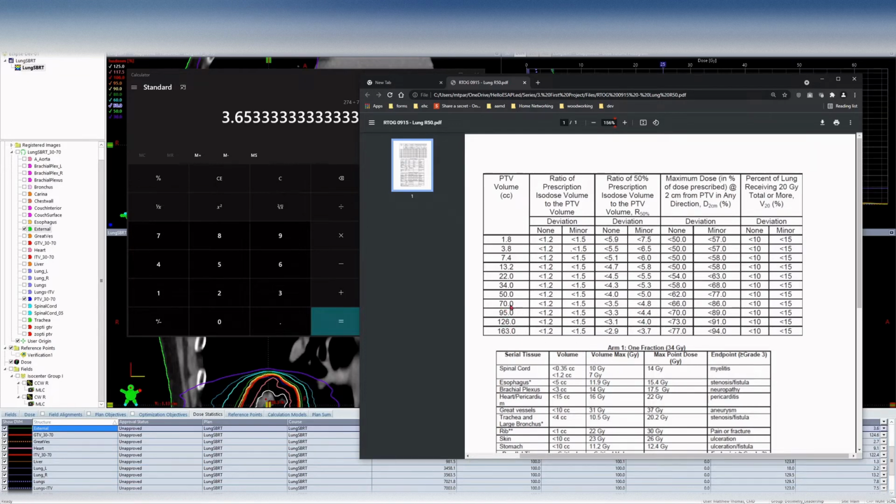And basically what you do is you interpolate between here and here and here and here. You know your volume, so then you need to calculate the interpolation value between 3.5 and 3.3. So that's another thing that we can and will do. We'll program that, so based on the PTV's volume, we'll be able to figure out programmatically what the ideal and the acceptable variation values should be, right?